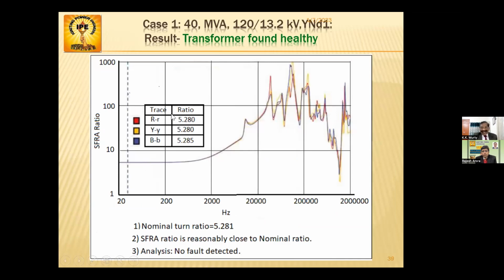This is the result of a healthy transformer. See, this 5.28 is the ratio R to R, and Y to Y is 5.280, and B to B is 5.285. So the curve is like this. They are almost the same. So the normal turn ratio is 5.28. The SFRA ratio is reasonably close to the nominal ratio. Analysis: no fault detected. Okay.